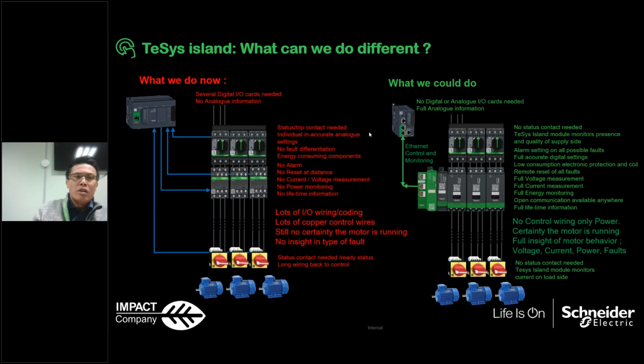So here we go. What can we do differently with and without the TeSys island? In the past, and even what we do today, we use a typical configuration of motor circuit breakers with contactors to control the motor. So we can basically only give a status, trip status or on-off status, to the PLC, but there are no fault differentiations. There is no individual analog setting. There is no energy consumption information for these individual motors. There is no alarm, no remote reset, no current or voltage measurement, no power monitoring, and no lifetime information. The only information you can have is the status of the contactors via the auxiliary contact block. So this is what we do today.